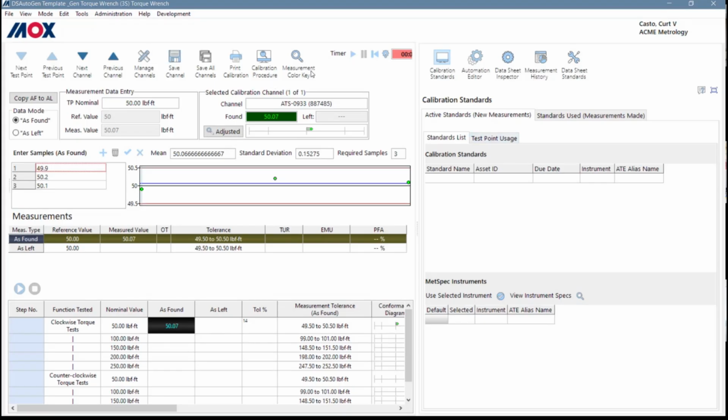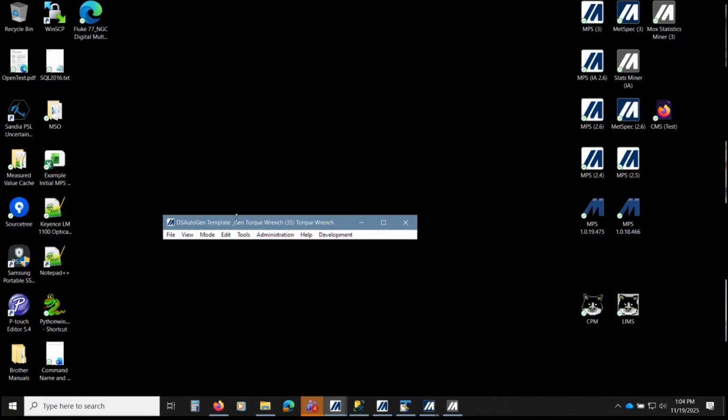Which means the uncertainty calculation is actually being done correctly, which most labs aren't doing, right? They're not taking that repeatability into account. It's not going into their budget. So you're getting a true uncertainty analysis at time of calibration. Right, so that's basically one example.